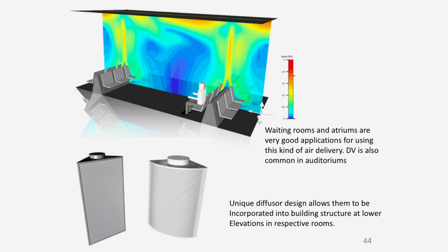So what we found, on slide 44, with those two diffusers on the lower left side, is that they can bring those down with ductwork in a column and deliver the air low at a warmer temperature, which saves a tremendous amount of money. Because if we're delivering air at 55 and now can use displacement ventilation to deliver air at 61 degrees, you save a lot of money and you get an effective infection prevention situation occurring. So if you deliver air low, it warms up immediately and starts to rise. So that thermal buoyancy begins to lift the air above the breathing zone.